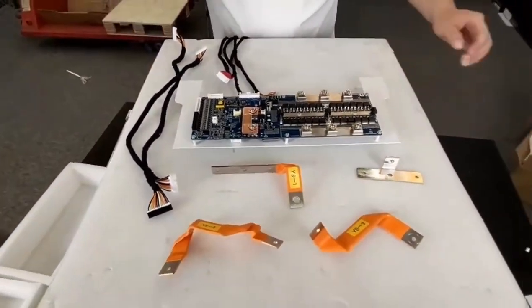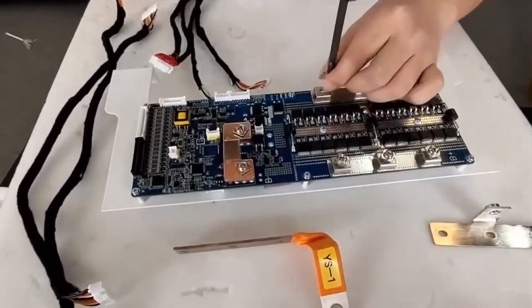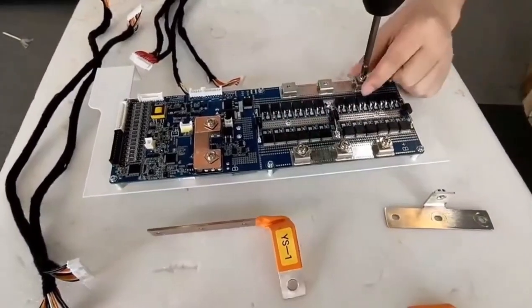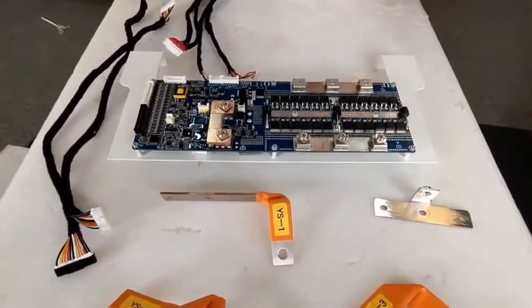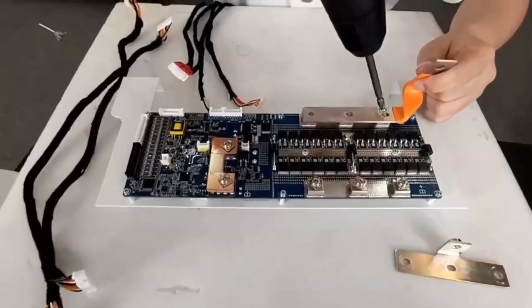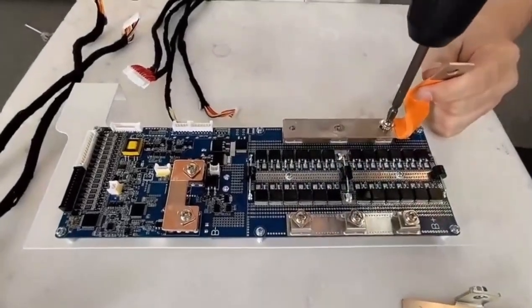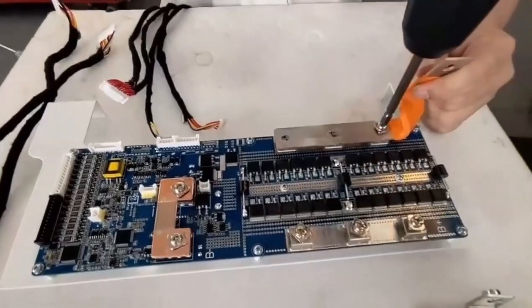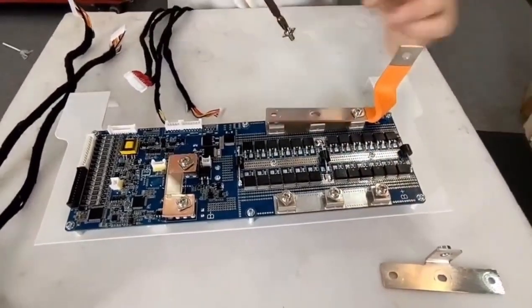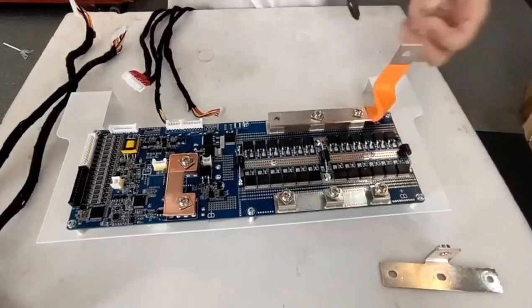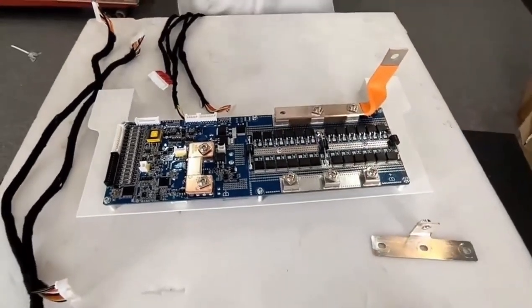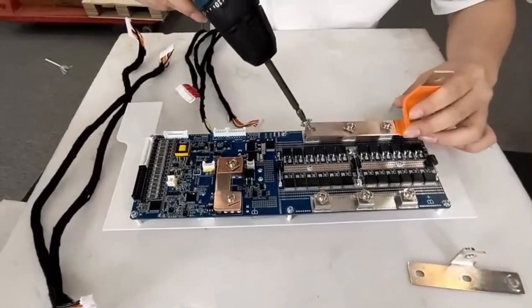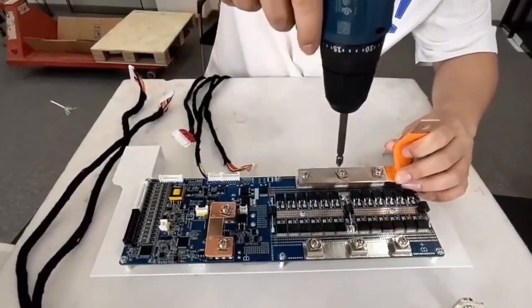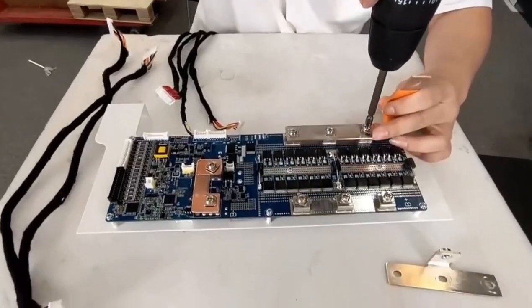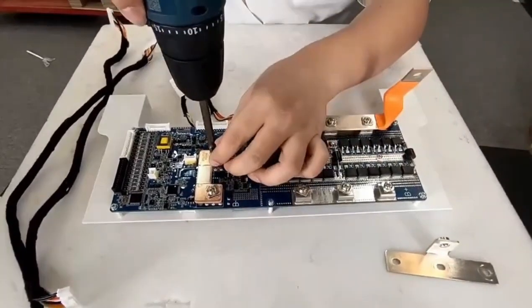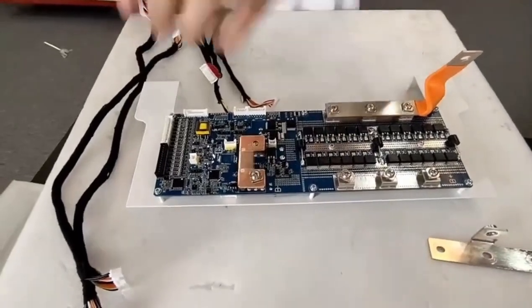So let's restart it. For this one, we need to see the force of the drive screw is about 6 Newton-meters. We need to ensure the force of the drive screw. We need to make the contact area between the BMS and the purple bus bar large enough.